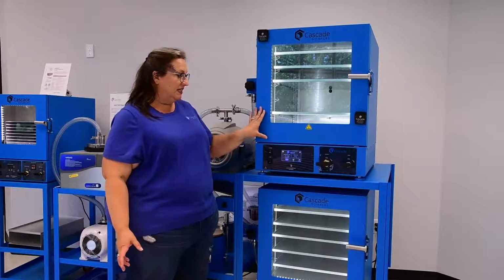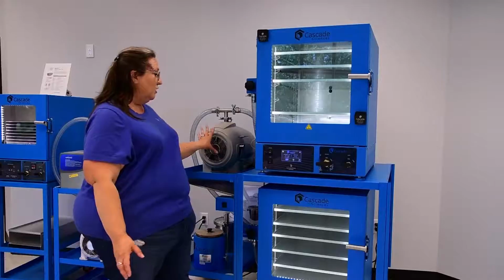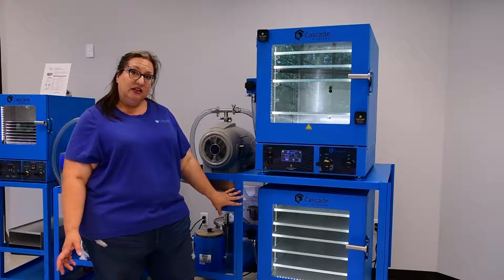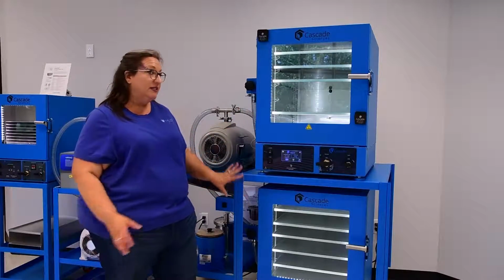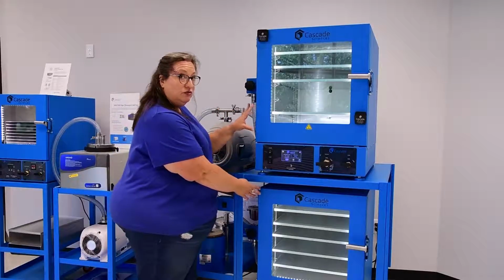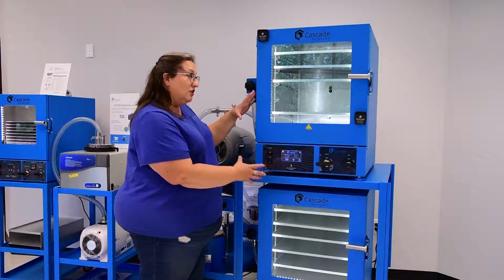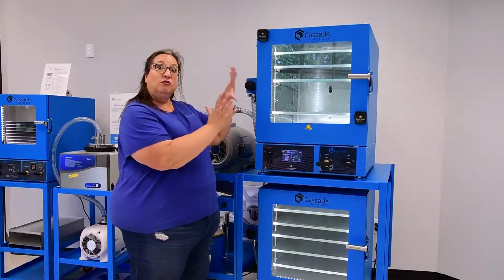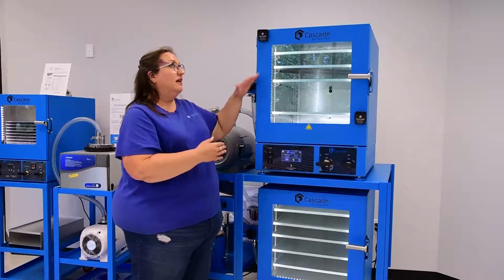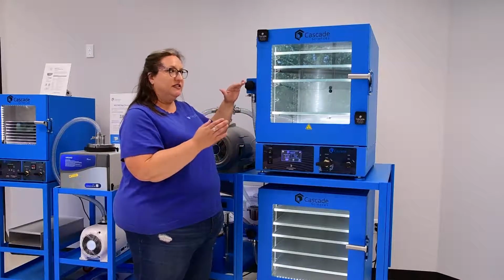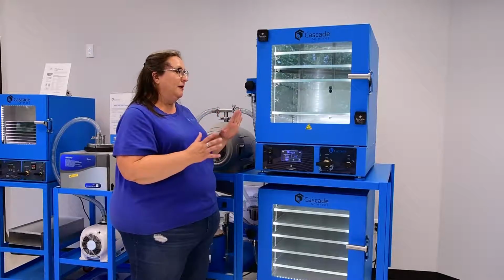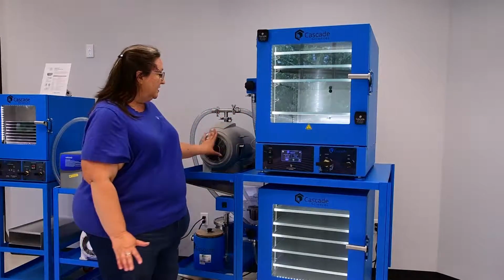What's fantastic is that by having 2 ovens sharing 1 pump, you have all the utility of 10 cubic feet of oven space, but the versatility of 2 separate chambers so that you can do that fill it and run it program instead of doing 1 or 2 shelves and then stopping and then doing 1 or 2 shelves and stopping. So I love this system.